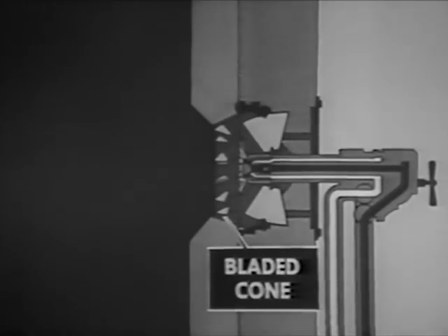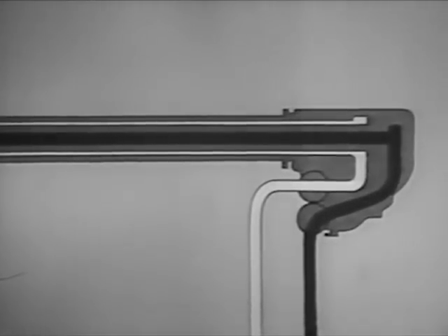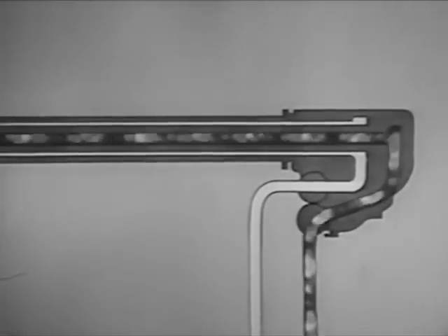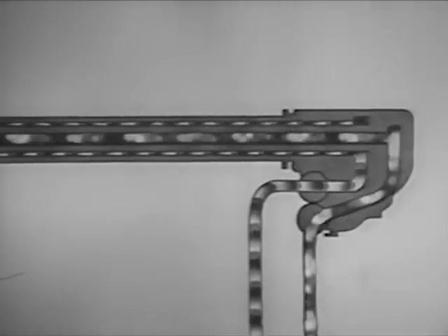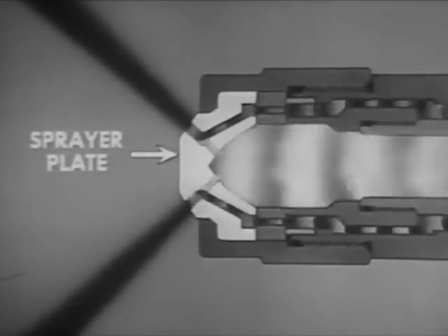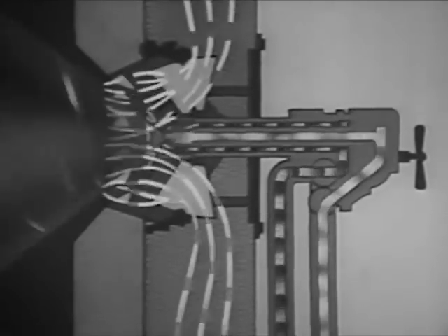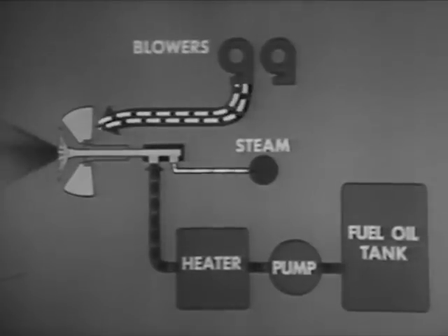The steam atomizing burner is similar in many respects to mechanical atomizing burners. It has an air register with diffuser, bladed cone, and air doors. However, the barrel of the burner has passages for both fuel oil and steam. High pressure steam passes through the central passage in the burner barrel, while oil under low pressure passes along outer passages. The steam heats the oil. The steam and oil mix in the sprayer plate, and the mixture passes through openings or jets in the plate and emerges as a fine mist. Meanwhile, the air from the forced draft blowers is entering the register and mixing with the oil spray.